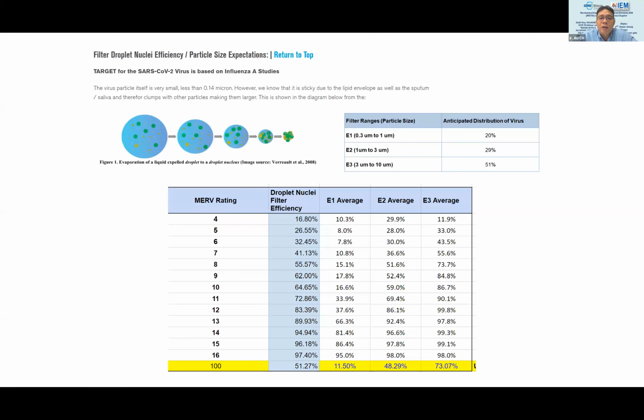Then how do we evaluate the filtration efficiency? In the same series of information, they used the influenza A distribution of virus in terms of particle size, because the virus may be small, 0.3 micrometer, but a lot of time it is attached to dust, or when people sneeze, their saliva, this human byproduct that comes out, breathing material, whatever we exhale from our nose, and of course some of the dust, some of the particles. That's why you have different distributions, and we realize that 50% of the virus pathogen can be in this range, 3 micrometer to 10 micrometer.